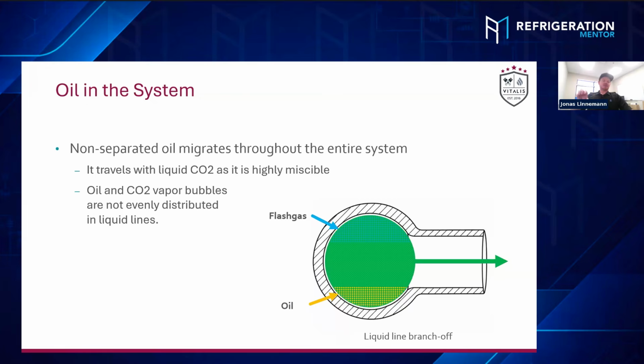The only thing on these flooded overfed systems is you need to figure out how to return the oil from that flooded circuit, right? Because you circulate the liquid all the time, and you also circulate and saturate more and more with refilling liquid CO2 into that loop. You're also refilling all the time more and more oil. So you would never get that back because you just pull the vapor out of those accumulator vessels. So there are different ways. They are like oil domes. There are these internal heat exchangers to boil oil bleeding off, whatever you do. But that's the more challenging part. The field installation is less challenging.